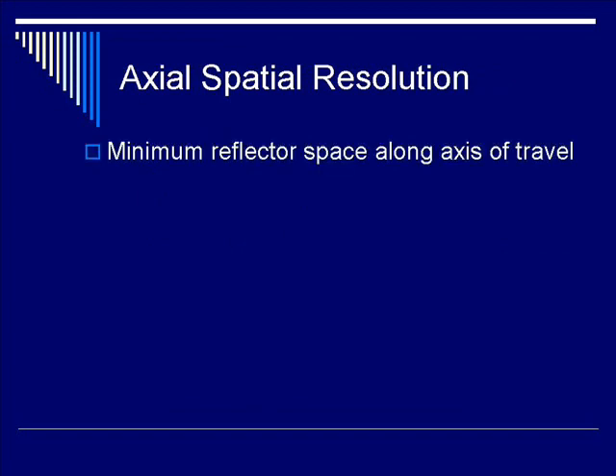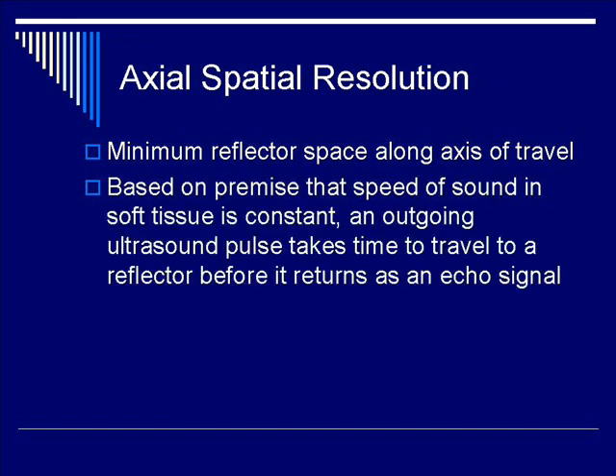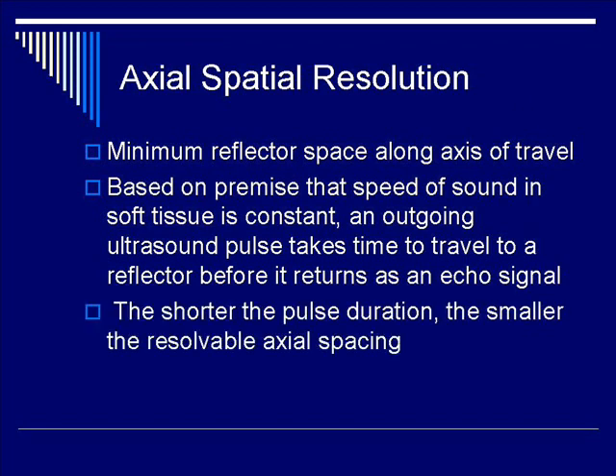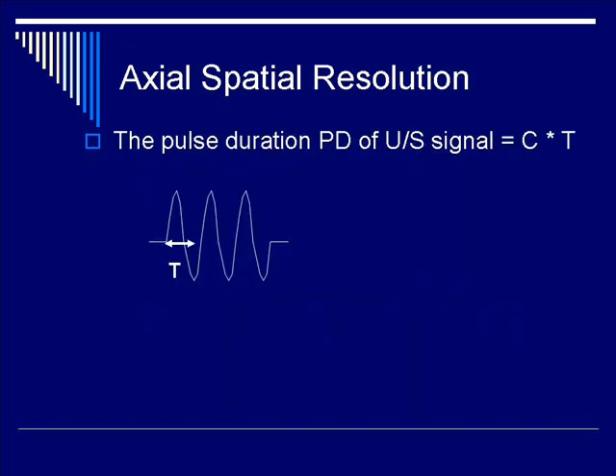Axial spatial resolution describes the minimum reflector spacing along the axis of travel. It's based on the premise that speed of sound is finite. An outgoing ultrasound pulse will take time to reach the reflector and also time to return as an echo signal. Therefore, the shorter the pulse duration, the smaller the resolvable axial spacing.